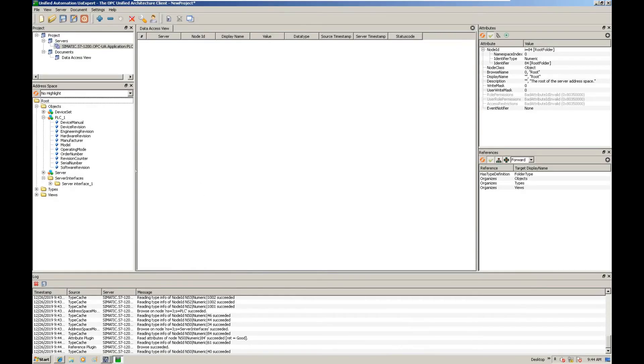Next we need to browse the data interface on this server. Because all the data is already placed into the server interface on the PLC side, we can see there is a folder named 'server interface'. The name is identical with the settings on the PLC side — it's 'server interface underscore 1'. The client has browsed and already found this server interface. We expand this folder to see all the data, then multi-select all of them and drag them to the data window.